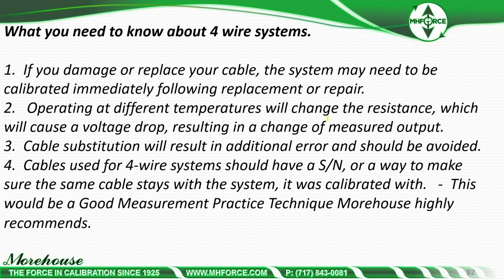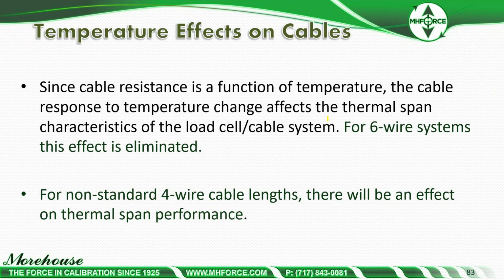So if you're using a 4-wire system, if you're using any of those meters that are 4-wire and you're switching cables or doing anything, switch to a 6-wire system immediately on the next cal. Don't continue to do it. Your errors are going to be huge. Since resistance is a function of temperature, the cable response to temperature change affects the thermal span characteristics of the load cell cable system. For 6-wire, that's eliminated. With 4-wire, there will be an effect.